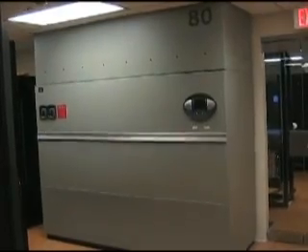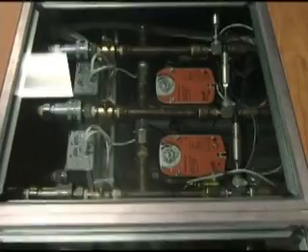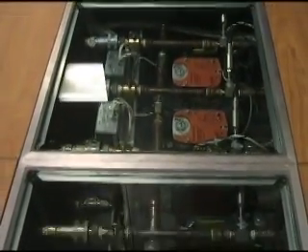Now, what kind of equipment can you control? Because it's an IT system, but you're linking back to the heating and cooling, right? We actually sense information from the environment and pull power and energy information off the IT equipment. We control the facility's equipment — things like the computer room air conditioning units. We can control the fan speed to apply more or less cooling into the room depending on the thermal load based on sensor information. We also have localized rack-level cooling on selected highly utilized devices. We can actually control how much liquid cooling or chilled water gets sent to those specific rack-level devices so that if a particular server is highly utilized and the temperature is increasing, we can control the water flow to maintain the same operational range.